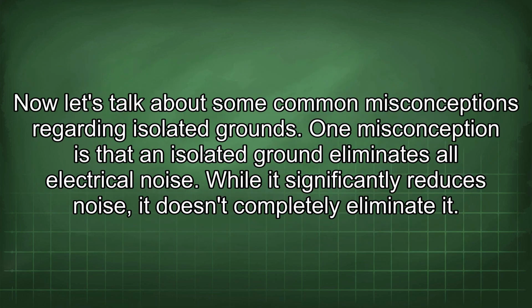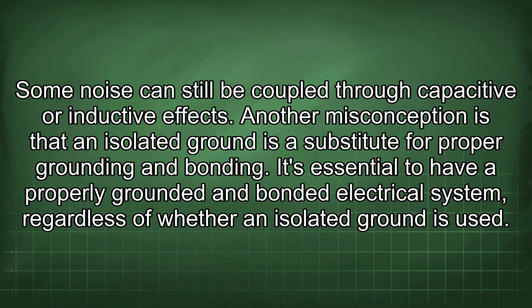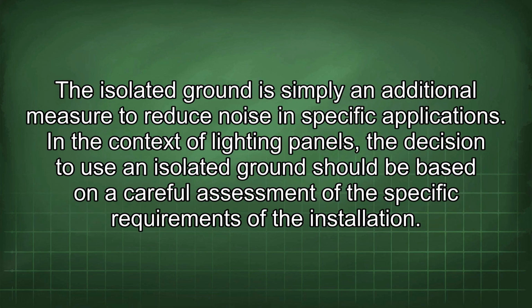Now let's talk about some common misconceptions regarding isolated grounds. One misconception is that an isolated ground eliminates all electrical noise. While it significantly reduces noise, it doesn't completely eliminate it. Some noise can still be coupled through capacitive or inductive effects. Another misconception is that an isolated ground is a substitute for proper grounding and bonding. It's essential to have a properly grounded and bonded electrical system, regardless of whether an isolated ground is used. The isolated ground is simply an additional measure to reduce noise in specific applications.